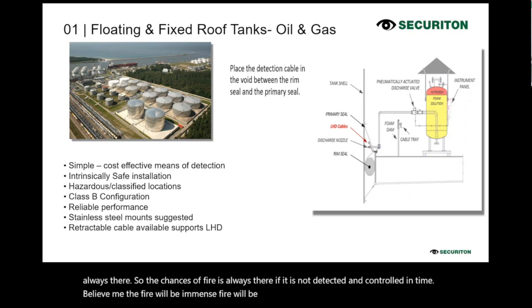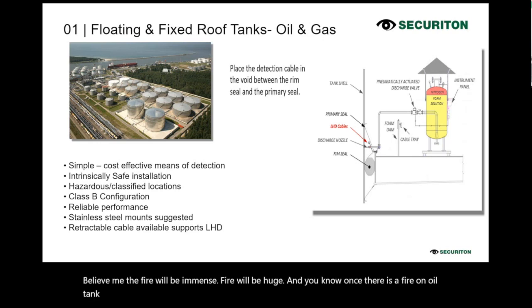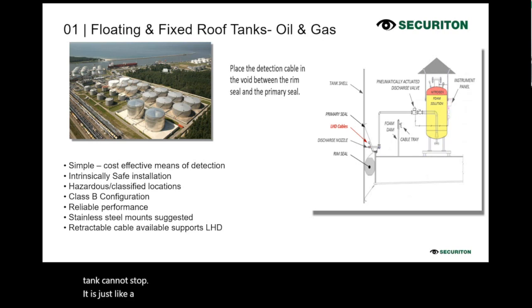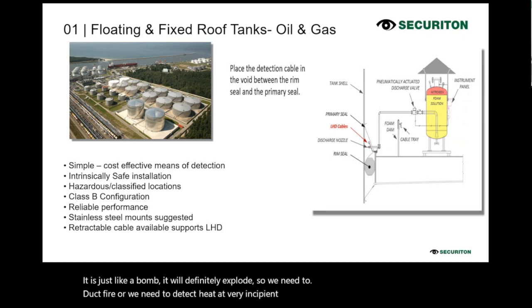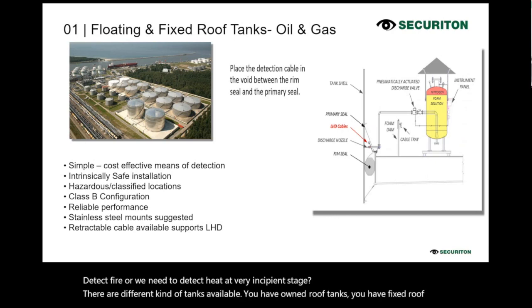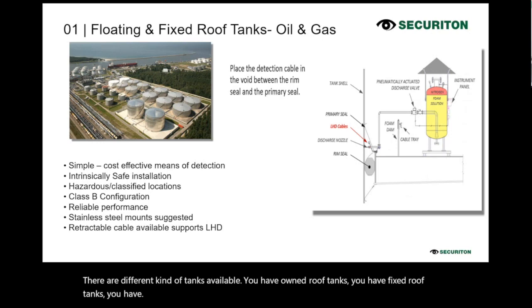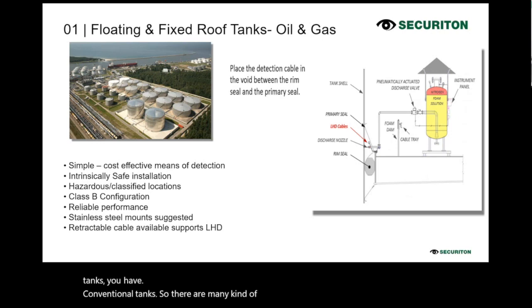And once there is a fire on an oil tank, you cannot stop it. It is just like a bomb. It will definitely explode. So we need to detect fire, or we need to detect heat, at a very incipient stage. There are different kinds of tanks available. You have cone roof tanks, fixed roof tanks, and conventional tanks. There are many kinds of tanks, but the solution is only a linear heat sensing system.